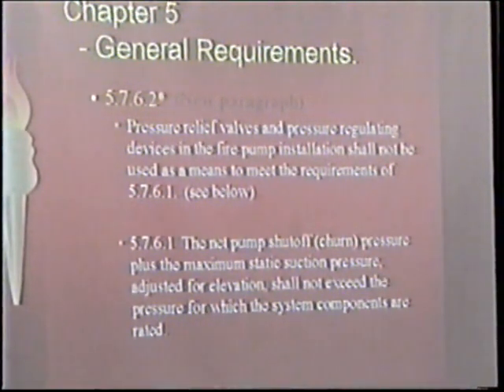And so I think what they're talking about there is they don't want a pressure regulating valve sitting in there with 200 pounds on the inlet side and 175 on the outlet side of it. And I think what they're saying is that if you're going to put a pressure regulating valve in, you need to do that on the individual floors. And that your discharge piping on the discharge of the pump has got to be rated for the pressure. There's actually another paragraph, I don't know if I put it in here, that says that it's not the intent to eliminate pressure reducing valves downstream of the pump discharge shutoff valve.